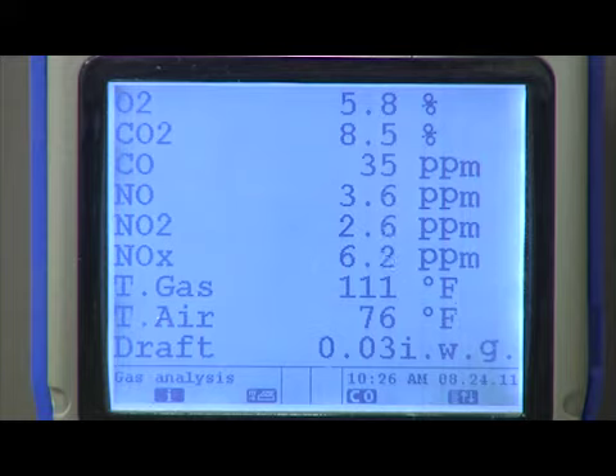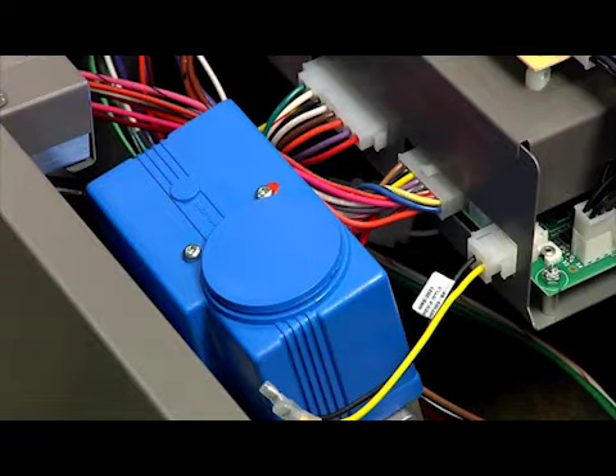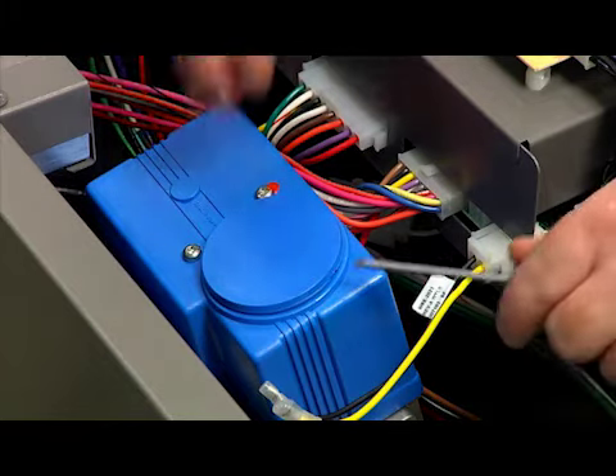If the CO2 and CO levels are still not within the specified range, repeat the adjustment procedure. If, after 4 adjustments, the CO2 and CO levels are still not within the specified range, revisit the other possible causes, or replace the gas valve. For the 601 through 801 models, locate the throttle adjustment screw under the blue cap on top of the gas valve.